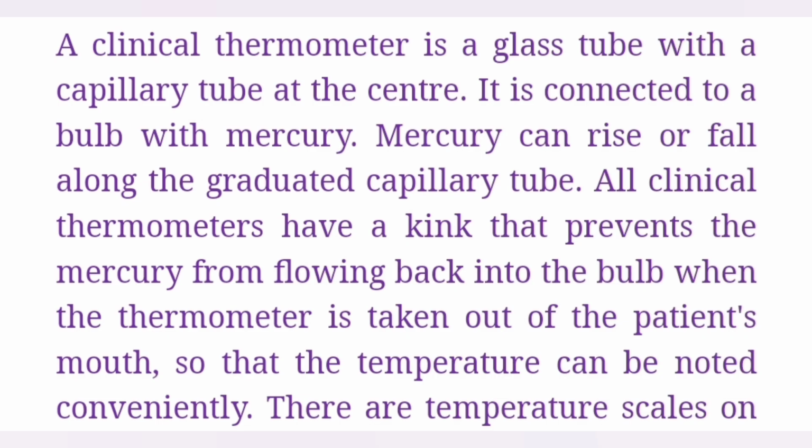A clinical thermometer is a glass tube with a capillary tube at the center. It is connected to a bulb with mercury. Mercury can rise or fall along the graduated capillary tube. All clinical thermometers have a kink that prevents the mercury from flowing back into the bulb when the thermometer is taken out of the patient's mouth, so that the temperature can be noted conveniently.